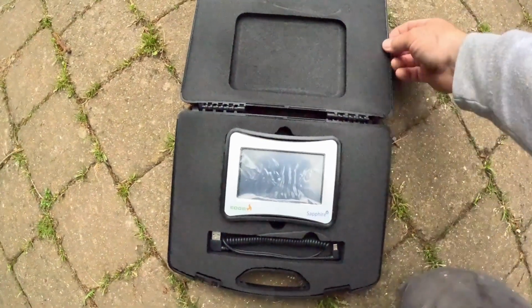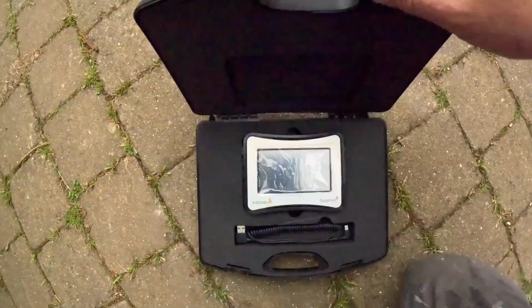So that is the Sapphire commissioning tool. You basically use this tool, plug it into the boiler, and set up the different modulation stages for the oil pump to change the modulation on the burner - which is where all the savings come from for your money.